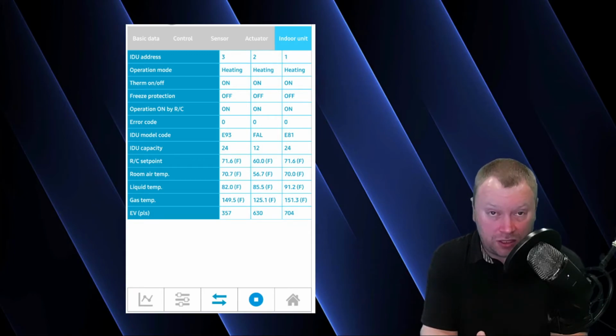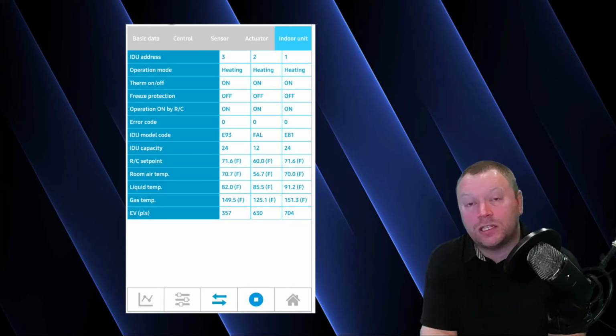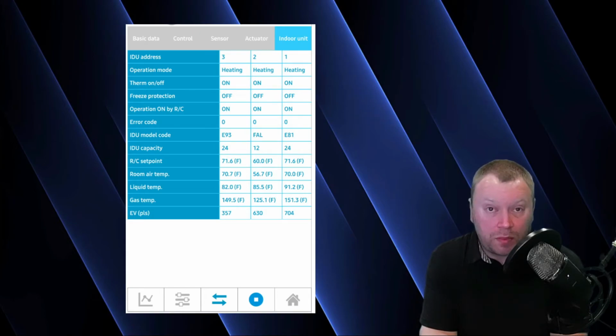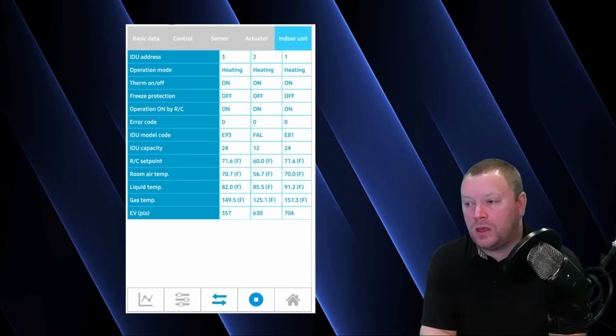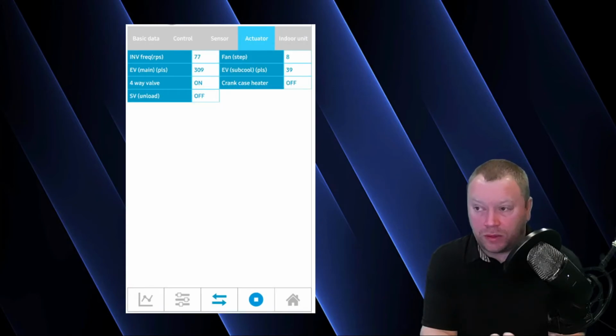It doesn't sit at 2,000 for very long because that typically indicates it's starving for refrigerant. It needs more refrigerant. Maybe there's a restriction in the system. Maybe you have a bad electronic expansion valve. Multiple things could be happening from that, which we'll talk about in another video. But when I'm back to the outdoor unit, I'm looking at my outdoor unit expansion valve position. It's at 309 pulses, which is fine.